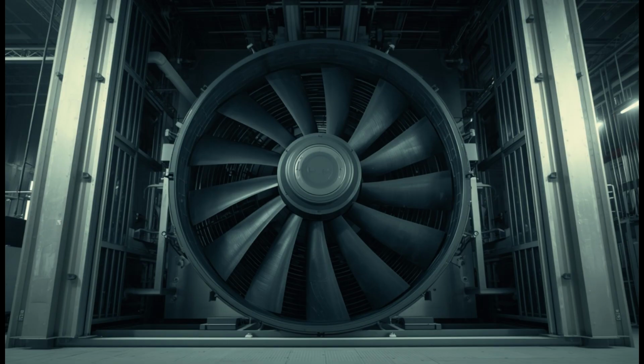Others, particularly larger installations, favor what engineers call a plenum fan, a design without the surrounding housing found on a centrifugal fan, instead spinning openly within the larger cabinet of the unit itself, drawing air in from all directions before releasing it forward. Still others abandon the idea of a single large fan altogether, relying instead on a fan array, a cluster of several smaller fan wheels mounted side by side, working together in unison to accomplish what a single large fan would otherwise do alone.